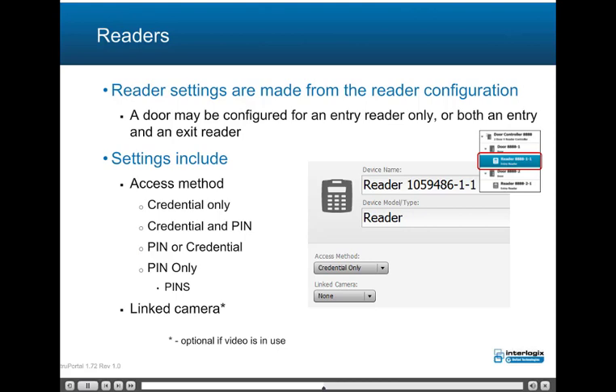Reader settings are made from the reader configuration. A door may be configured for an entry reader only or both an entry and exit reader. Settings include access method: credential only, credential and PIN, or link camera. Note that TruePortal does not support credential or PIN nor PIN only access methods.